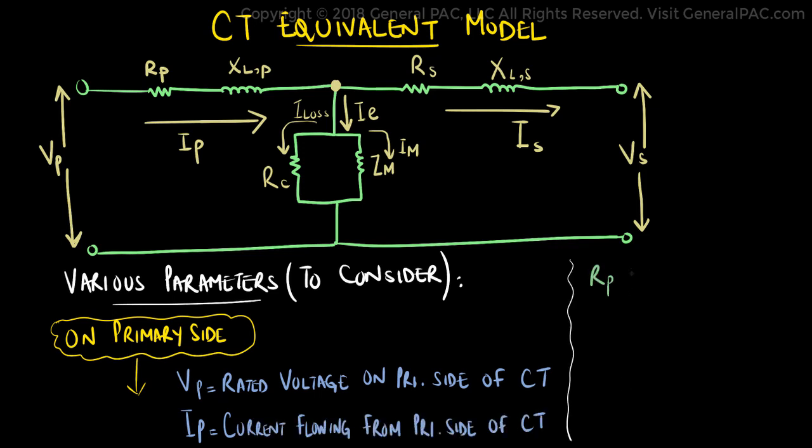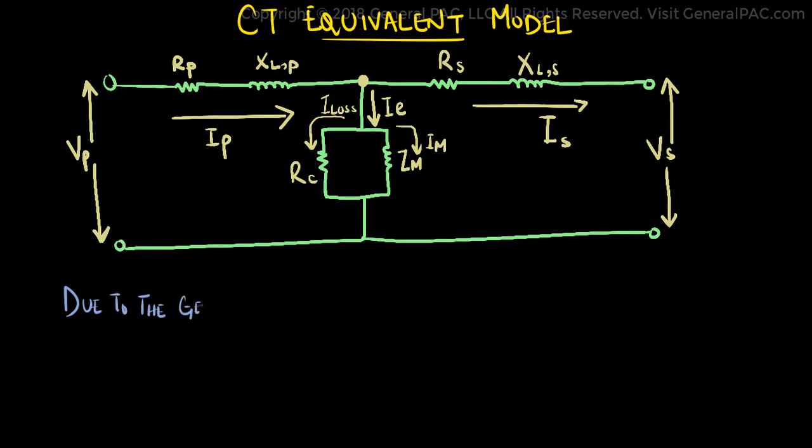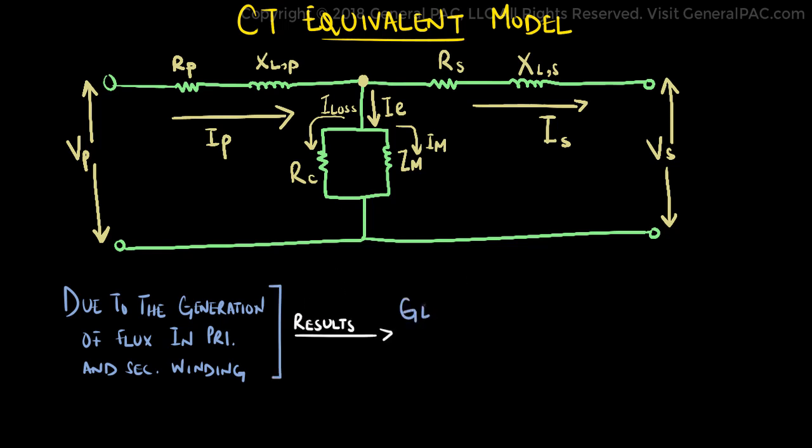The resistance components, RP and RS, are impedance parameters driven by CT construction, and due to the generation of flux in the primary and secondary windings, this results in the generation of a leakage reactance, which can be observed in the equivalent model on both sides.